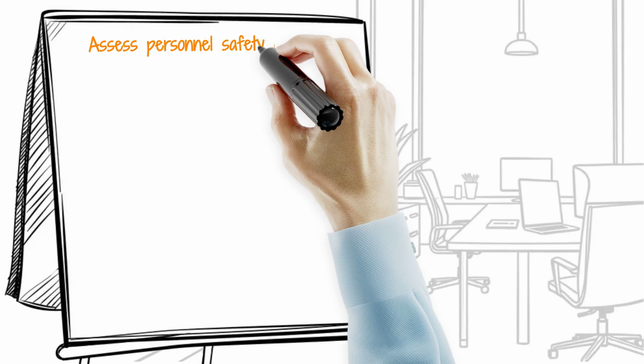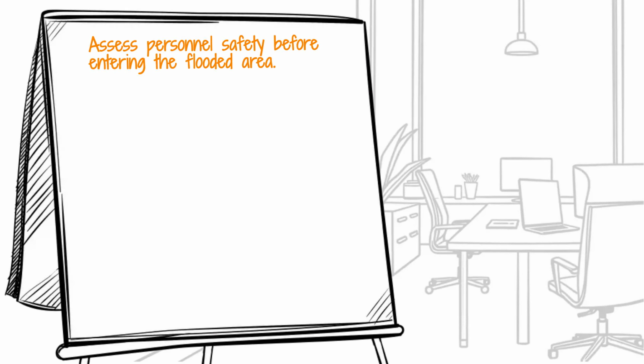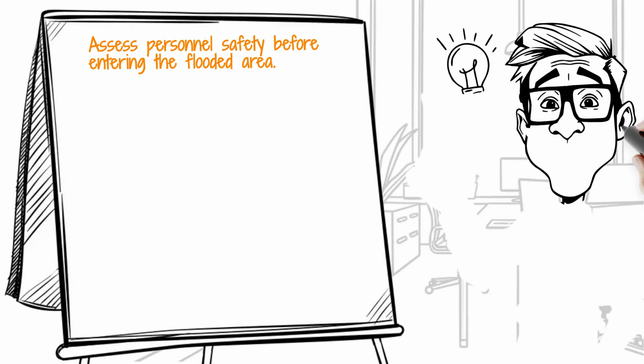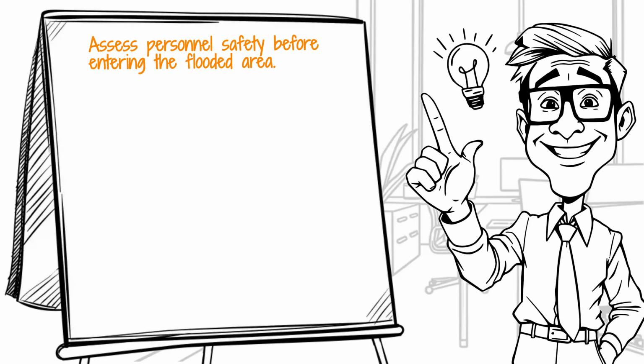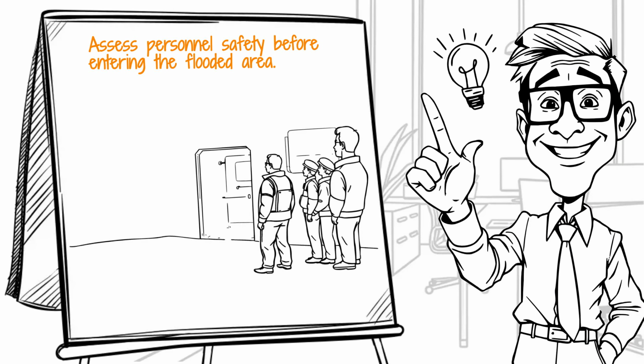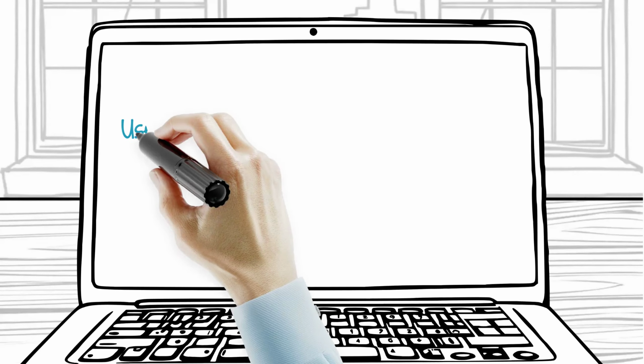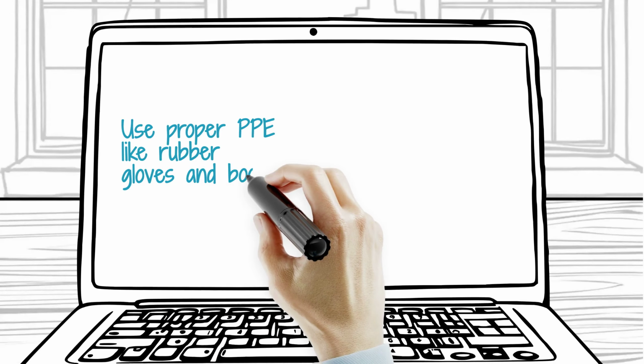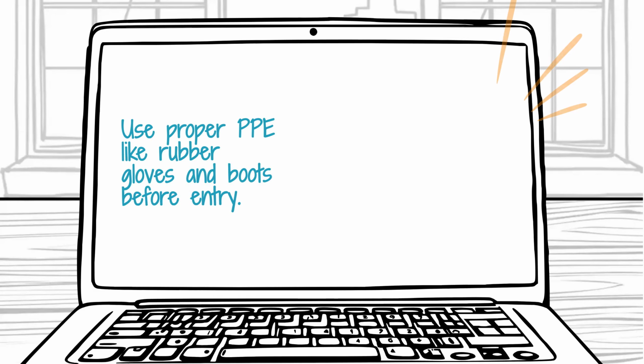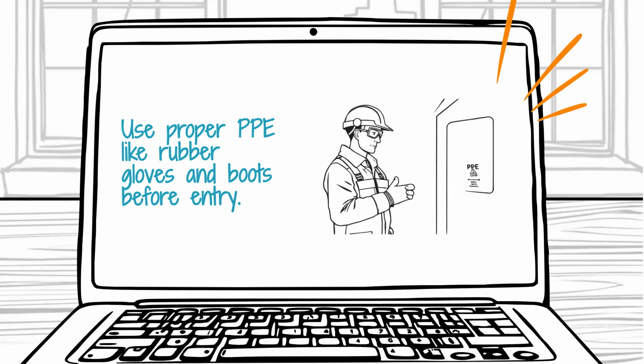Once the power is confirmed isolated, assess the risk. Do not allow personnel to stand in water, even if the power is supposedly off, until the source of flooding is controlled. Only personnel wearing appropriate safety gear, including insulating rubber gloves and boots, should enter the area. If the water contains contaminants like oil or chemicals, additional PPE is necessary.